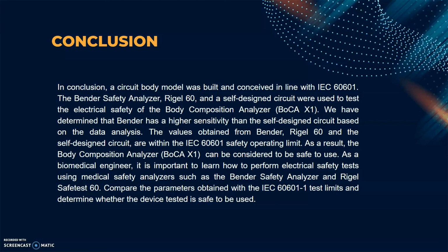As a biomedical engineer, it is important to learn how to perform electrical safety tests using medical safety analyzers such as the Bender safety analyzer and Rigel 60, compare the parameters obtained with the IEC 60601-1 test limits, and determine whether the device tested is safe to be used.